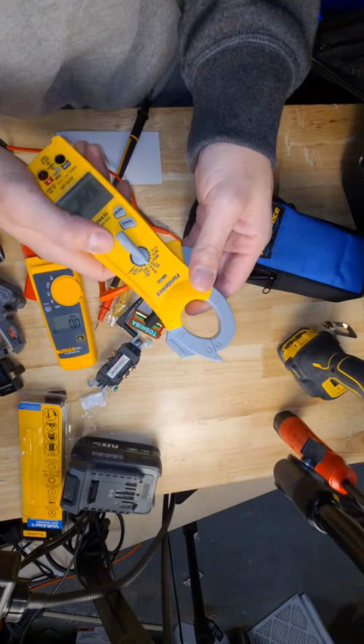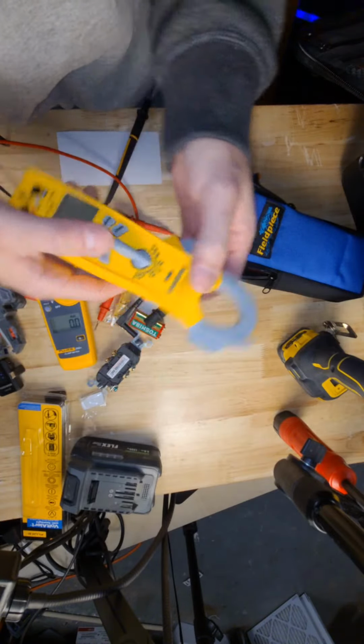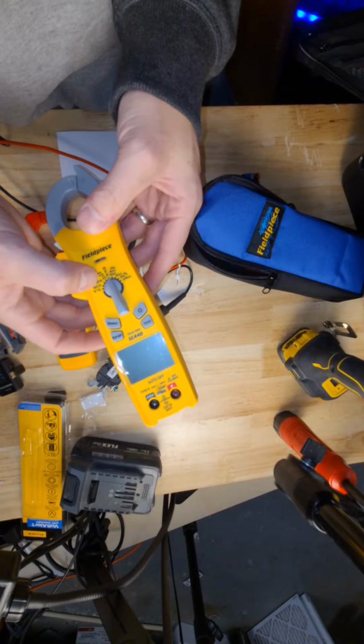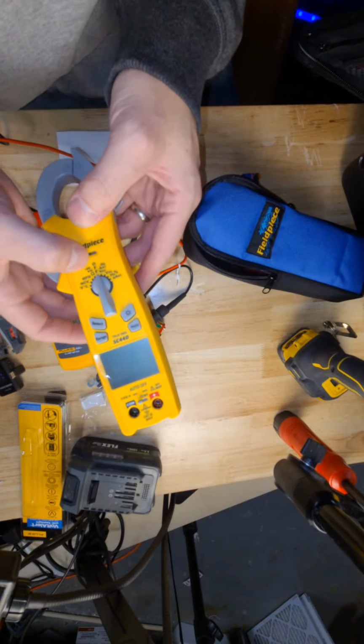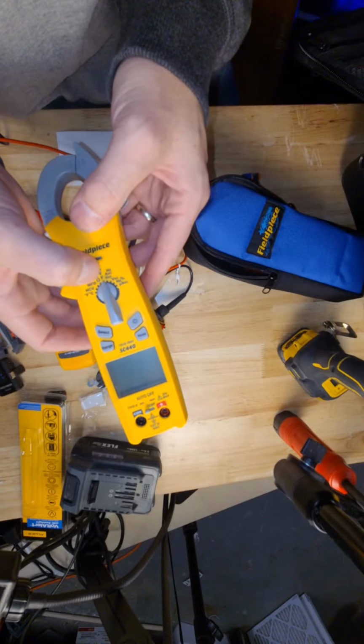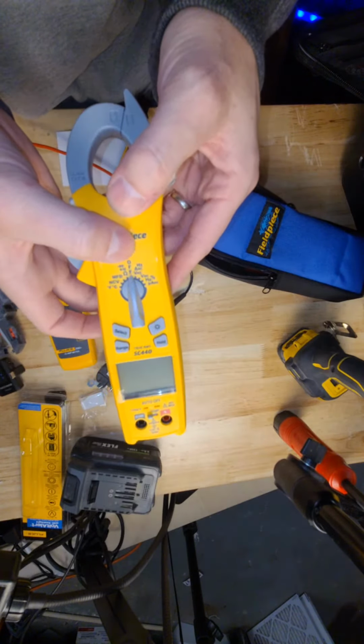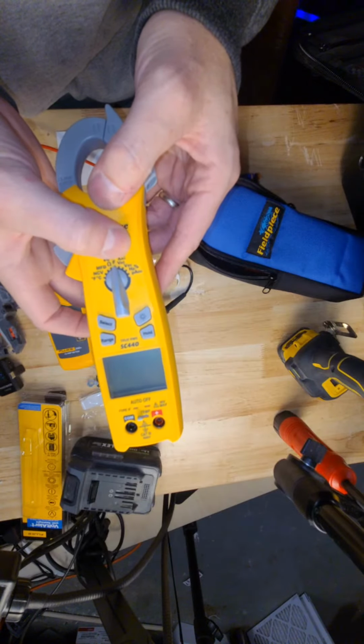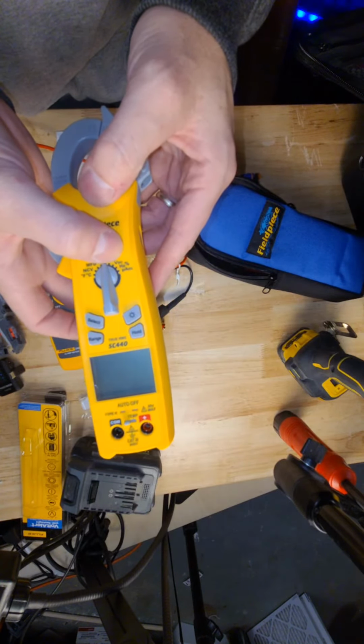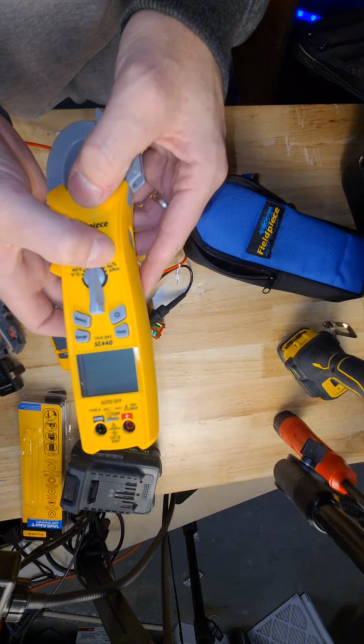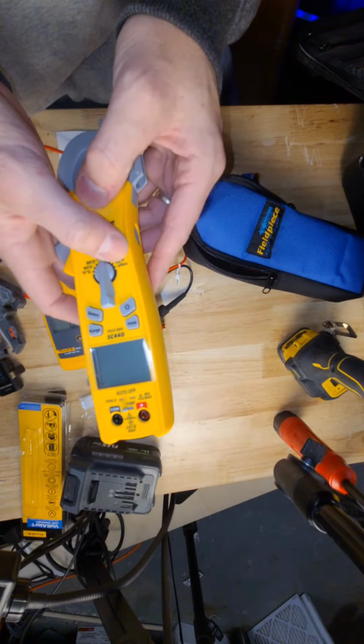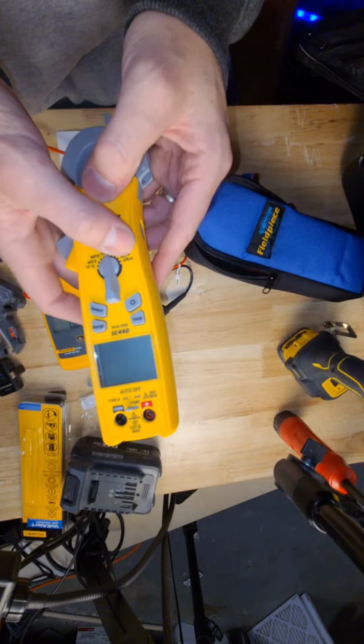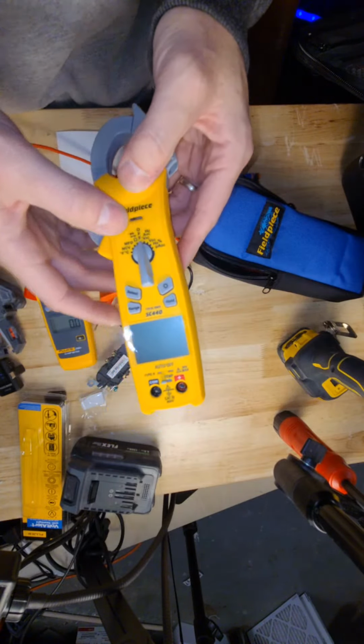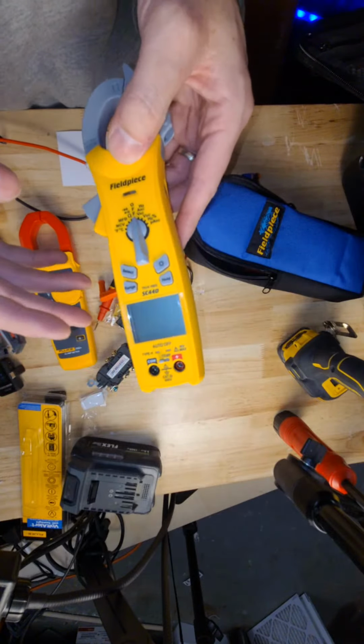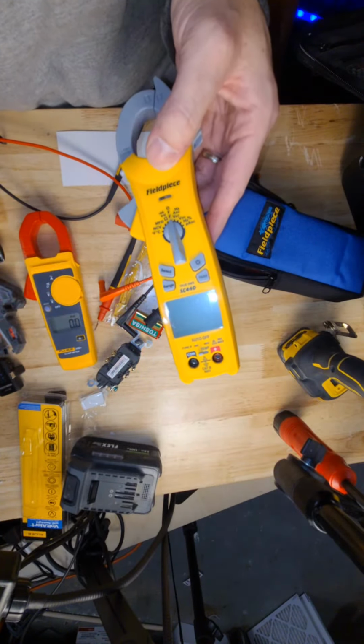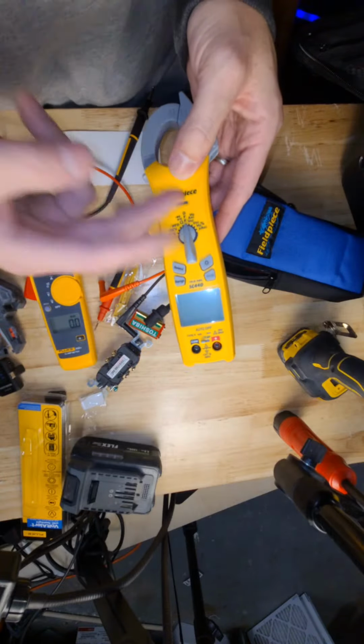Not too big, it's got some range. We've got temperature, non-contact voltage, microfarads. Then you got diode, continuity, and ohms. Then you've got the off, the hertz, the amperage AC, the volts AC, the volts DC, the hertz, so it does frequency. And then you get something called microamps DC, which is useful for heater controls, because that's how your furnace knows gas and heat are flowing, basically as a flame sensor.